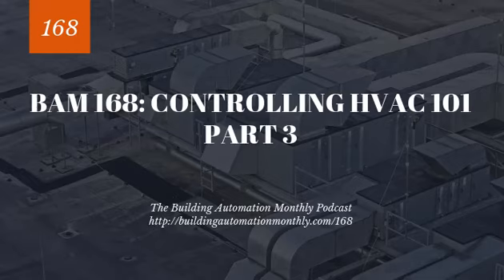Now, in the real world, doing this is a whole other matter. You can do this by utilizing economizers within your air handlers, making sure you're maximizing the use of economizers, but then you introduce issues like, should we be driving an economizer based off of dry bulb or enthalpy, because are we introducing a bunch of moisture into our building, which takes a bunch of energy to remove anyways? So you can kind of see the circular logic here, and one of the reasons why I was hesitant as to if I wanted to explain this or not.